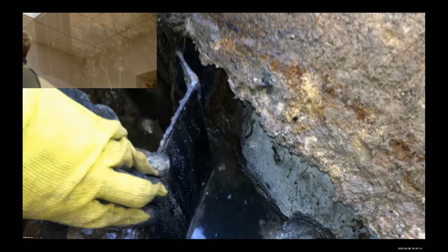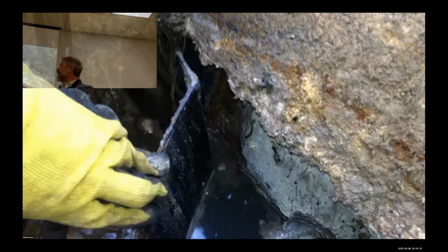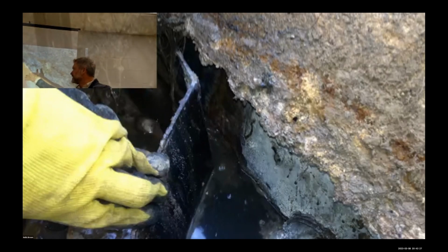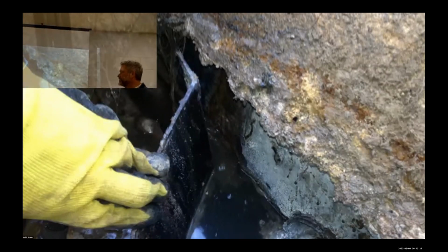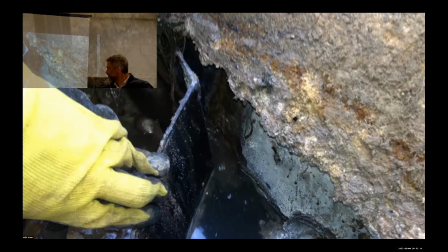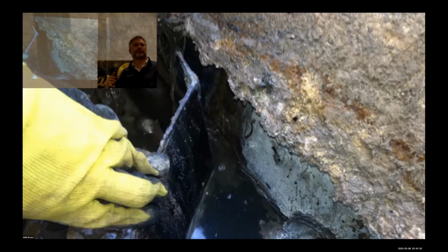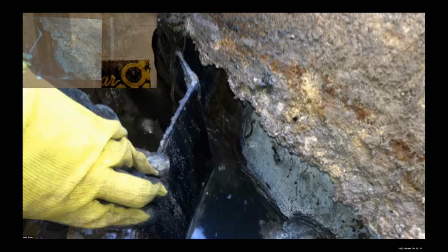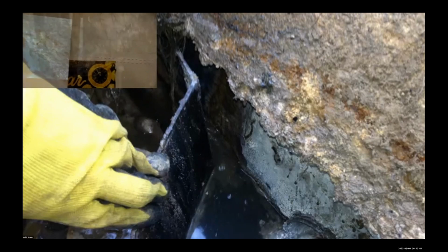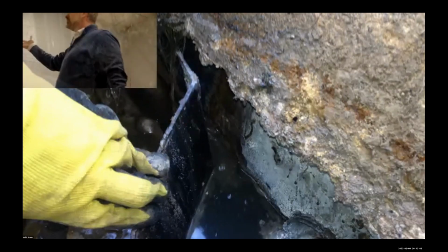I like showing this. So, back baffles. It's showing you all these T's, that PVC T is what I've been describing and showing. Sometimes it's not PVC, sometimes it's terracotta or cast iron. In Anne Arundel County, especially, and other places too, they put this kind of black sheet over top of the baffle. This is a line going out and they just bolt the sheet over so that those scum levels can't escape right out. It's 18 inches down, it acts just like a baffle. The water has to come out up and over. It's engineered as you would expect.